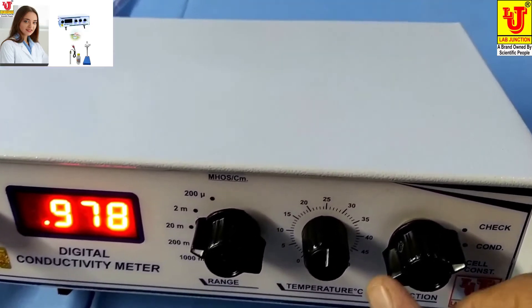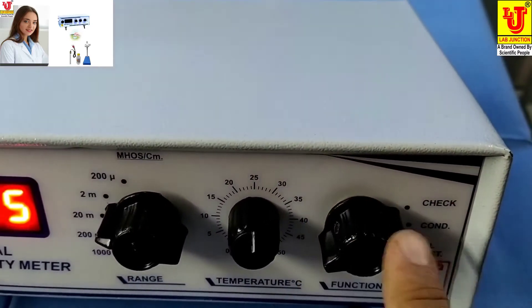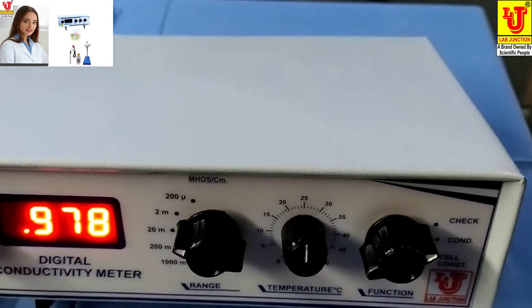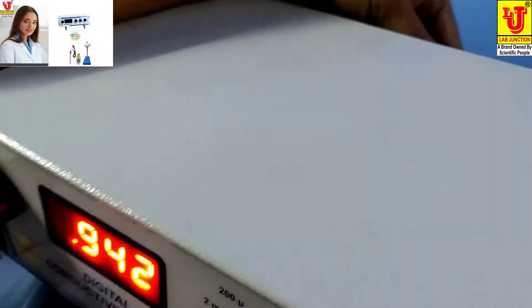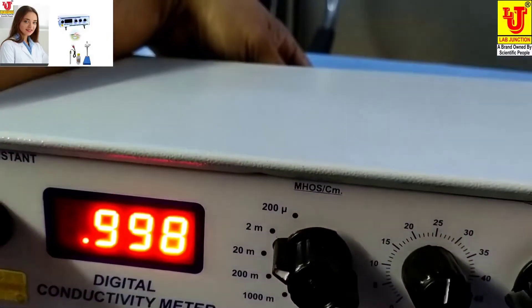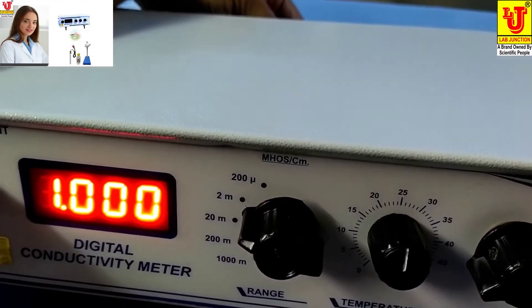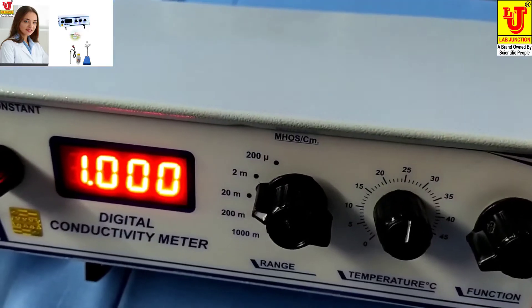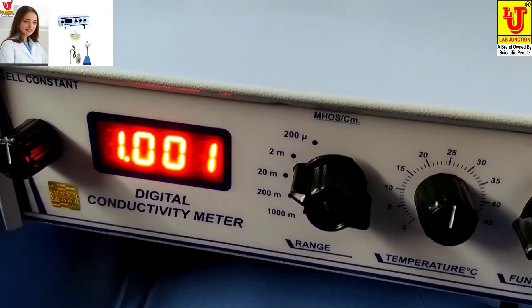First, you have to set the function control to check position. On the back side, the cal knob is there. You have to set it to 1.000. If it is blinking, you can set it again.